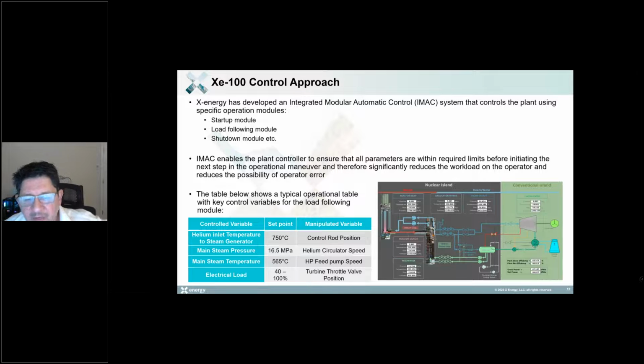The table below here also just shows how simple our control scheme has been designed. We've literally only got 4 control variables: the helium inlet temperature to the steam generator, the main steam pressure, the main steam temperature, and the electrical load. And as I mentioned, what you see on the right-hand side where I'm circling my mouse, that's the main steam control valve to the turbine. The customer can do with that valve what they want, and the plant will merely react to the temperature and pressure in that feed line.